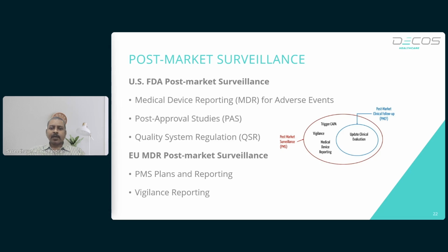Vigilance reporting, where immediate reporting of serious incidents affecting patient safety is mandatory. Timelines for reporting depend on the severity of the incident. When safety concerns arise, manufacturers must take field safety corrective actions (FSCA), such as recalls or product modifications to address the risk. Post-market clinical follow-up (PMCF) involves conducting ongoing clinical studies to gather real-world data on the performance and safety of a device.